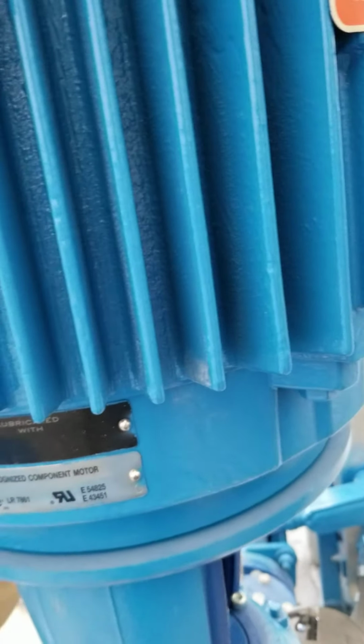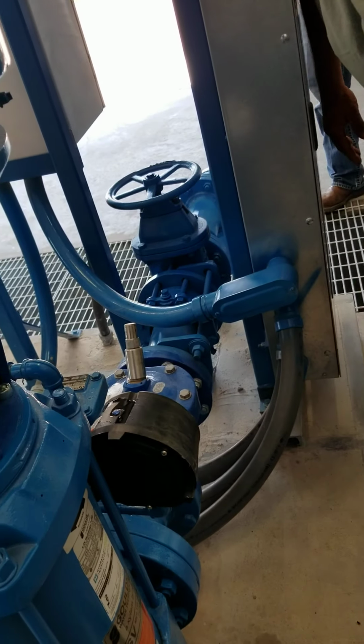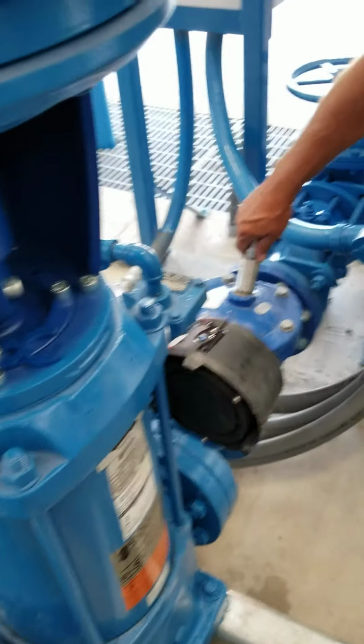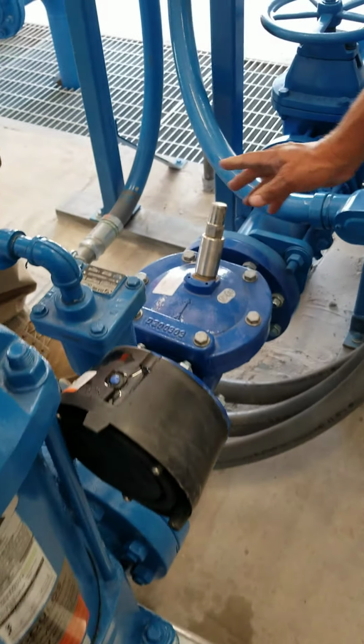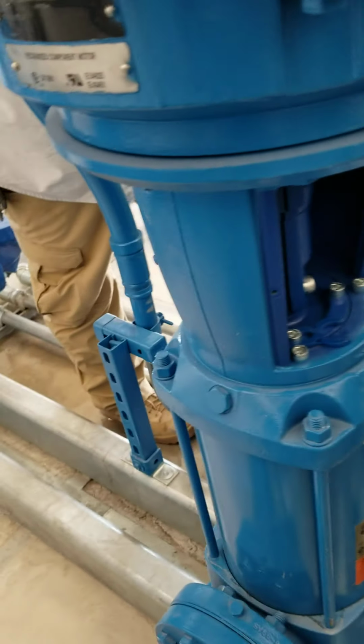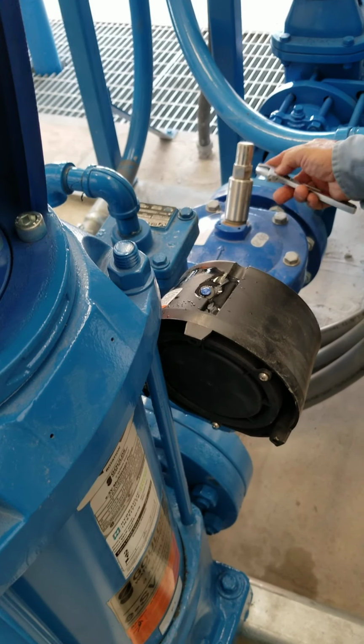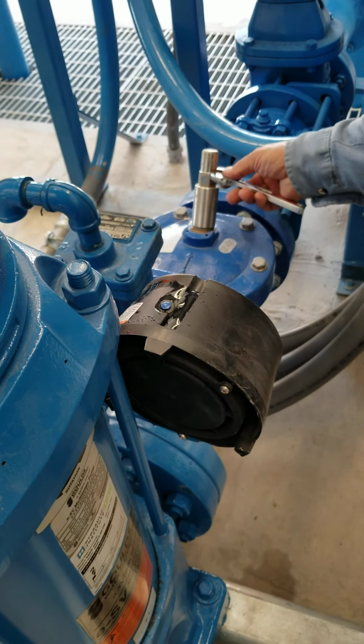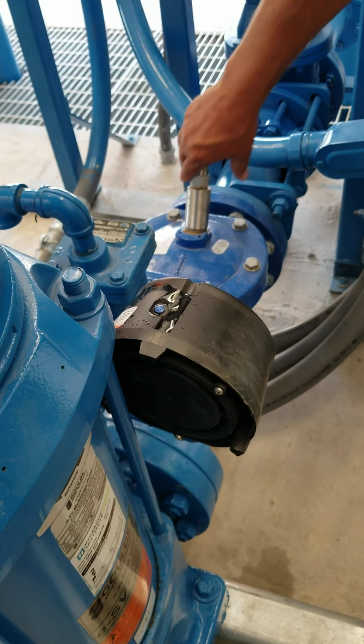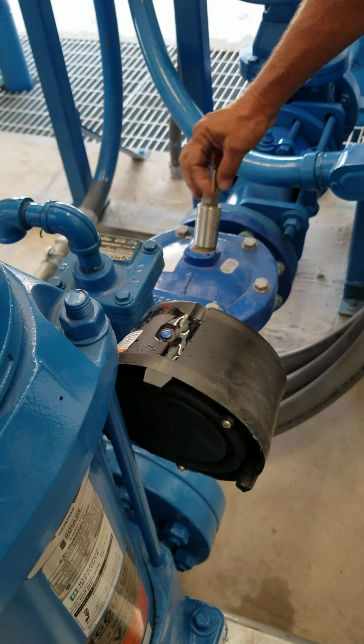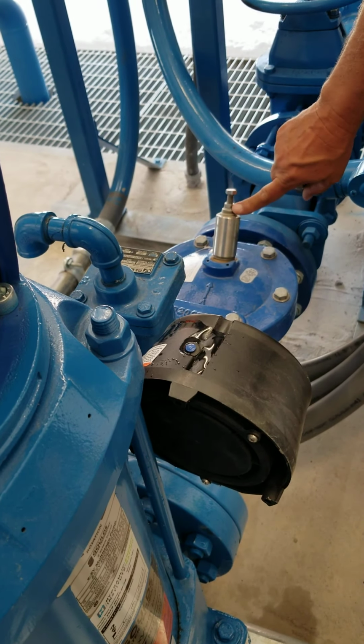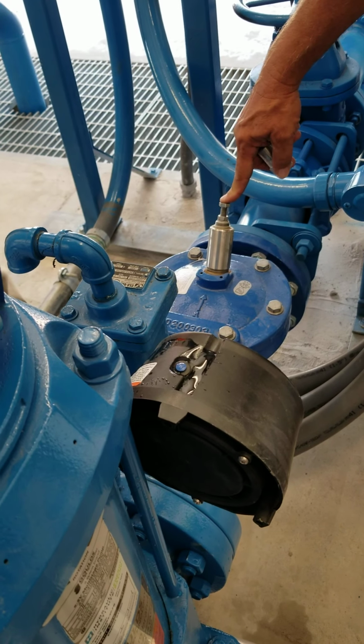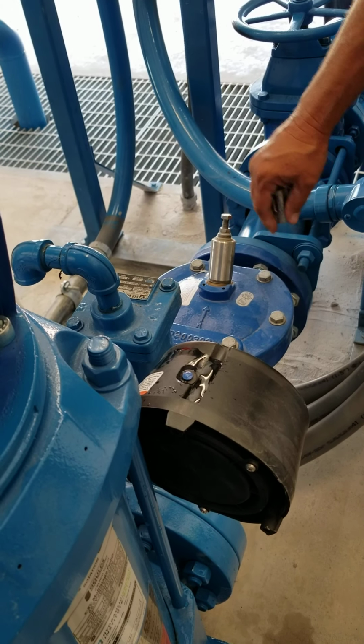And then this is your air release. They're not going to work a lot once you're in operation. This is a surge buster check valve. This is to control the closing speed. So right now we're okay. It's like a Cla-Val almost, like PRVs without the solenoids and stuff. It's just got a little spring in it. Locking nut. So down is faster, and then lock it back down.